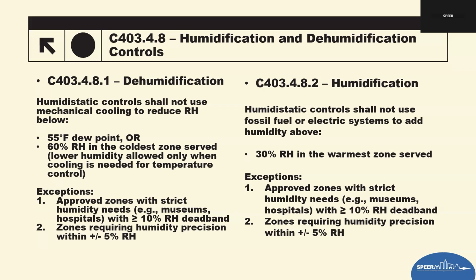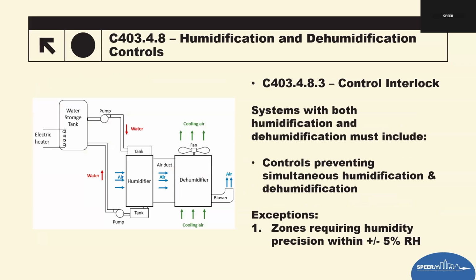And then humidification limits. On the humidification side, the code prohibits using fossil fuel or electric humidification to raise relative humidity above 30% in the warmest zones served. That'll be something you have to figure out when you're looking at it from a plan review. This prevents unnecessary humidification during times when indoor humidity can create mold or comfort issues. Again, these exceptions apply to very specific occupancy types. So look at those and make sure you're checking that before calling that out.